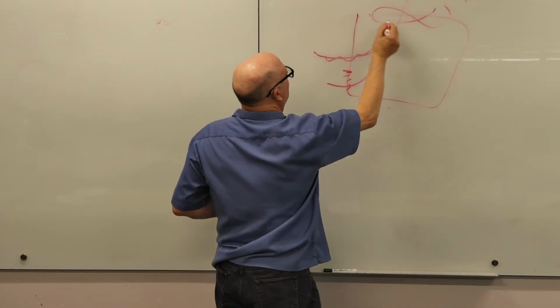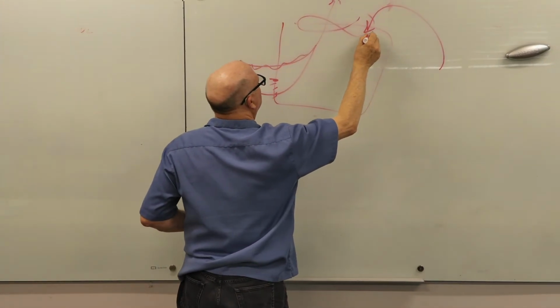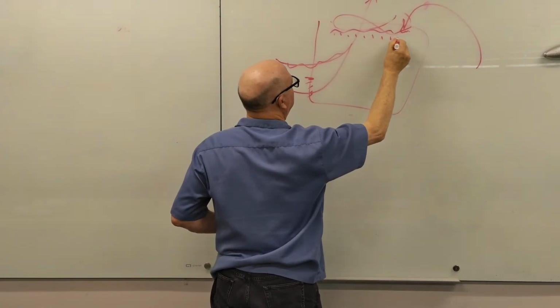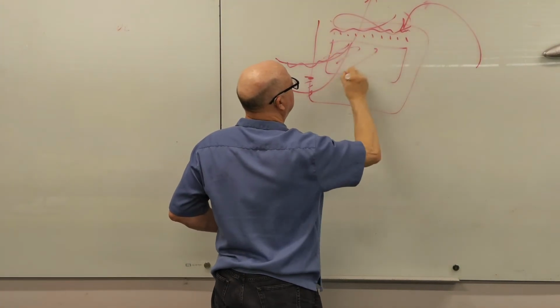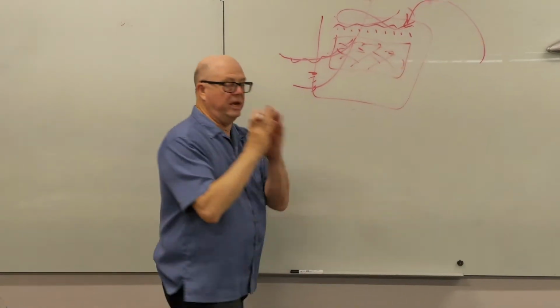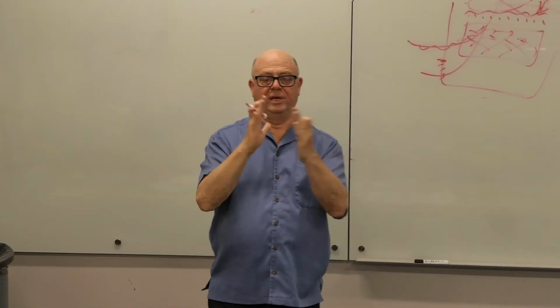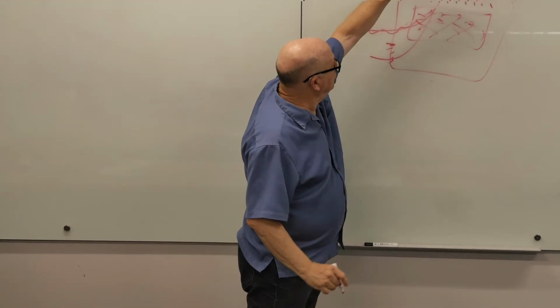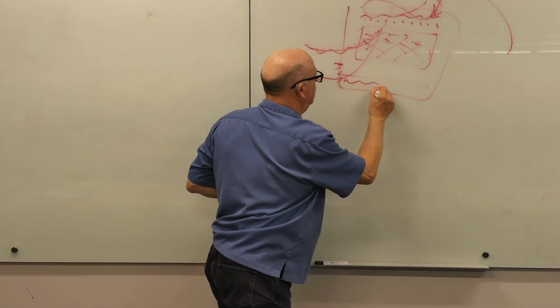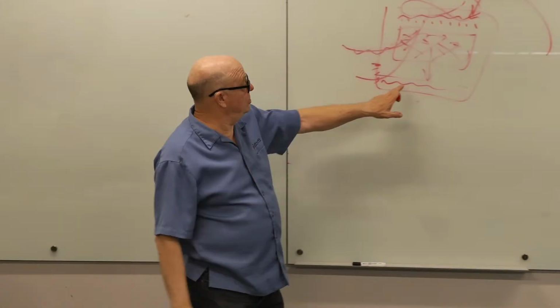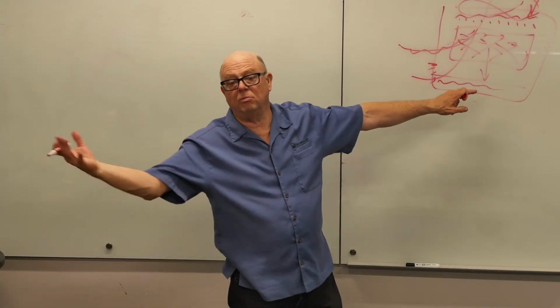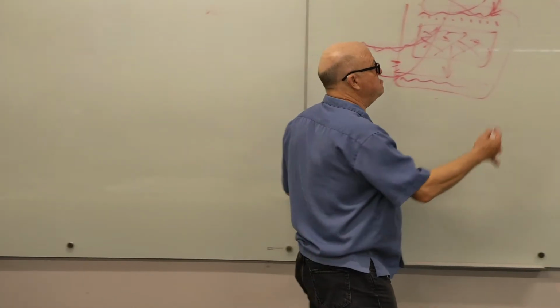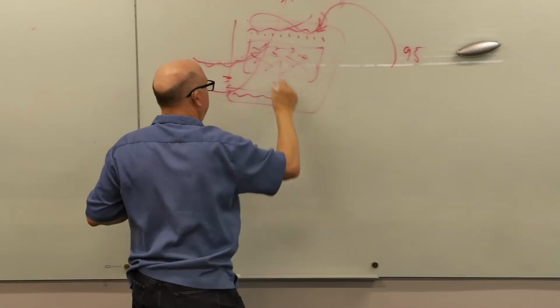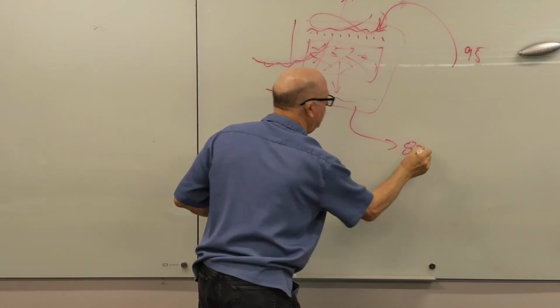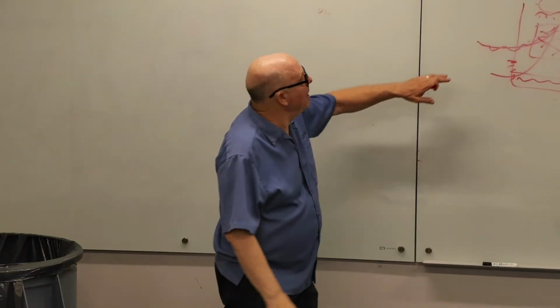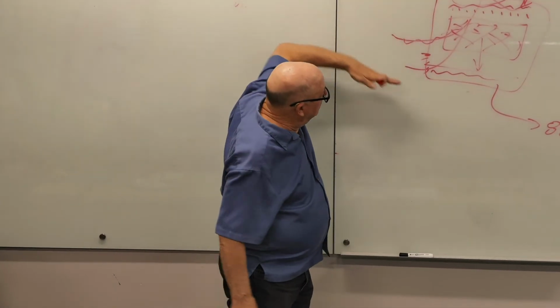You guys are great. So the return water comes to the cooling tower. You've got some kind of a spray tree or tray or something that's dripping it down. It goes through the fill, which is like honeycomb, right? Or maybe it's like a whole bunch of vertical plates together. The air is counterflow. It's coming down here to the sump. It's trickling down. And the goal is to get this water down to a temperature that we can send back to the chiller. On a design day, it might be coming back at 95 and you might be cooling it to 85. Common numbers, okay? So, counterflow.